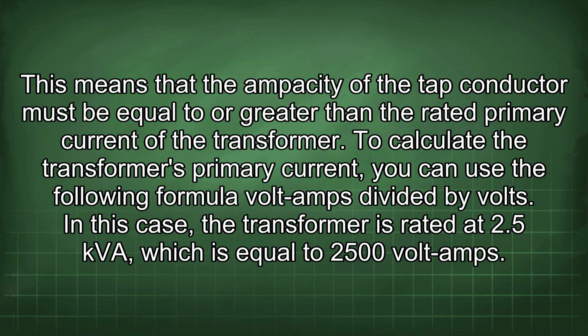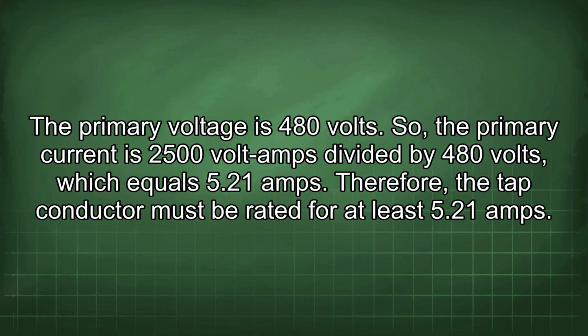This means that the ampacity of the tap conductor must be equal to or greater than the rated primary current of the transformer. To calculate the transformer's primary current, you can use the following formula: volt amps divided by volts. In this case, the transformer is rated at 2.5 kVA, which is equal to 2500 volt amps. The primary voltage is 480 volts. So, the primary current is 2500 volt amps divided by 480 volts, which equals 5.21 amps. Therefore, the tap conductor must be rated for at least 5.21 amps.